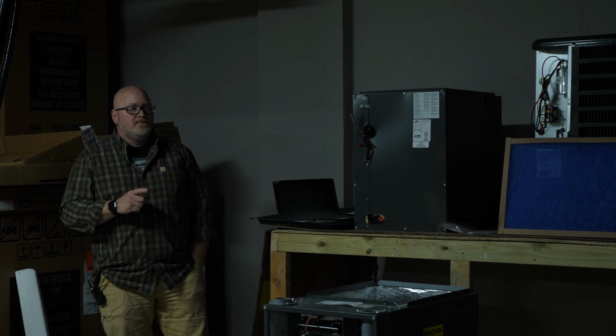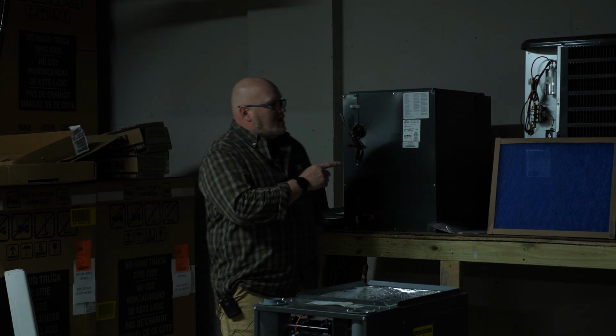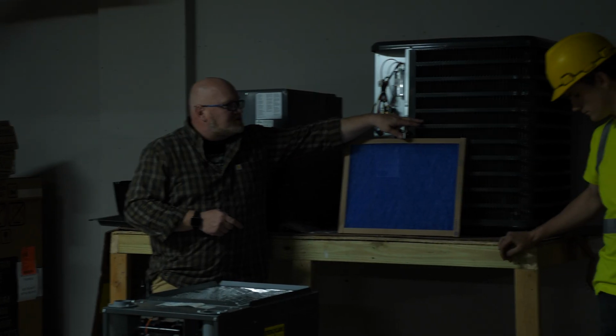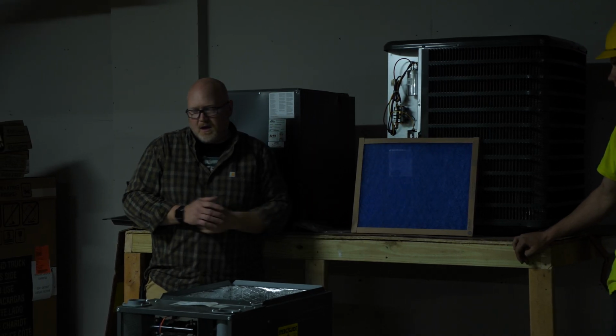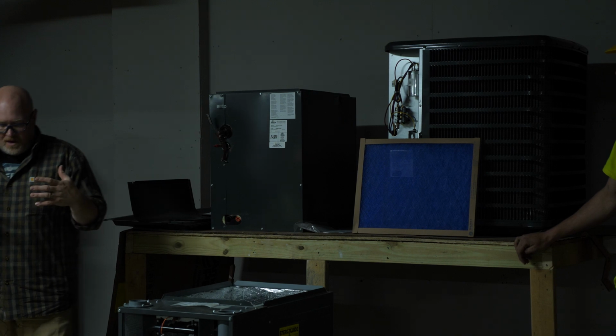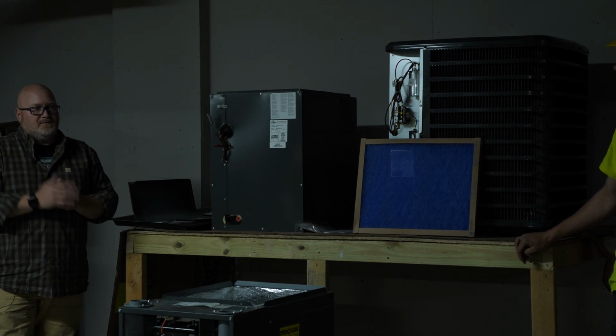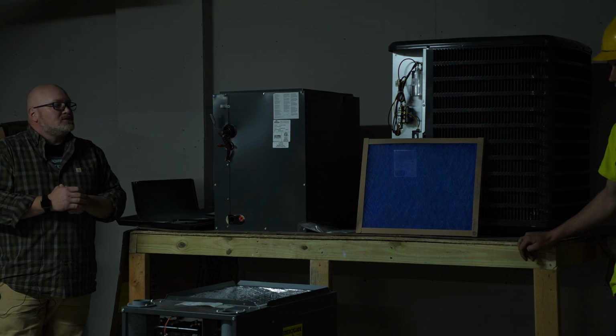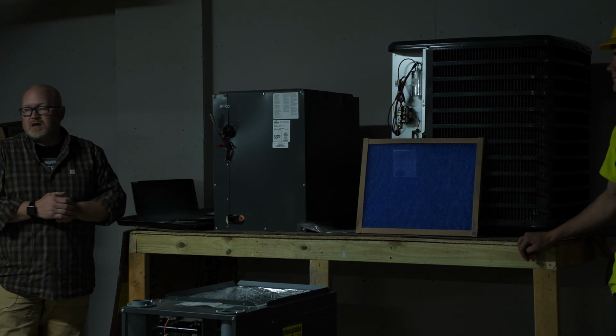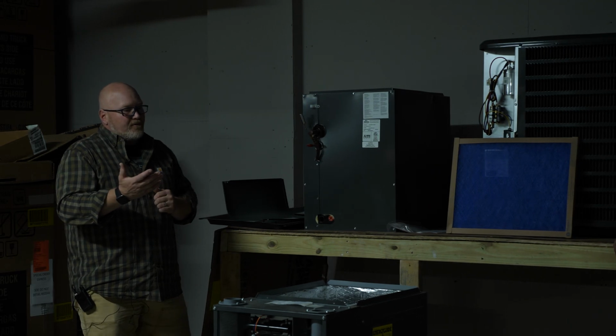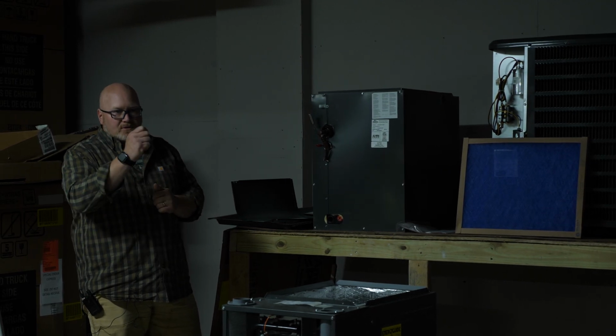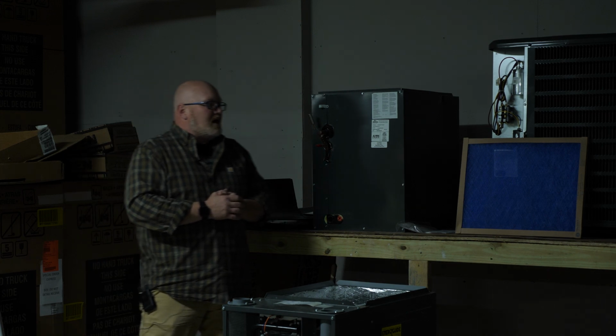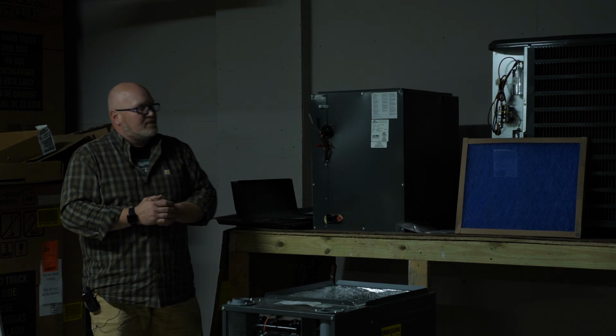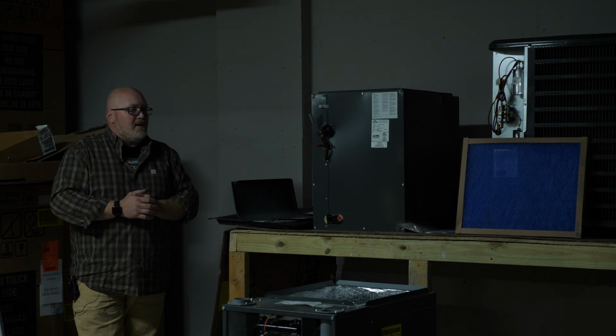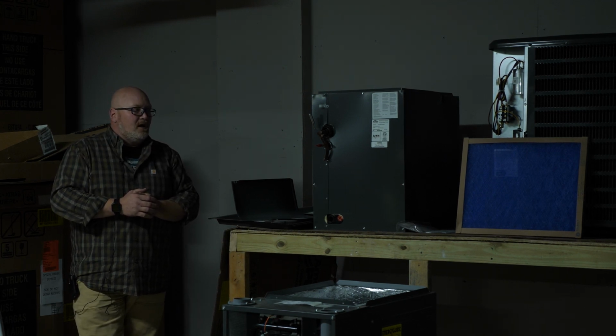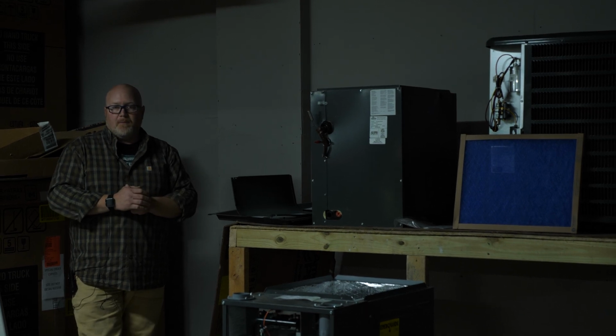What you don't want to do is bend the fins on these coils. If you come in closely at some point, you can see that these condenser coils are surrounded by a bunch of fins, and the fins will fold over very easily. So make sure that as you're cleaning it, you're not damaging the fins. If you fold over fins, they do have a tool called a fin comb. You can straighten out the fins. Otherwise, making sure that your outside condenser coil is clean and your inside filter is clean are the two biggest things you can do right off the bat, service-wise.